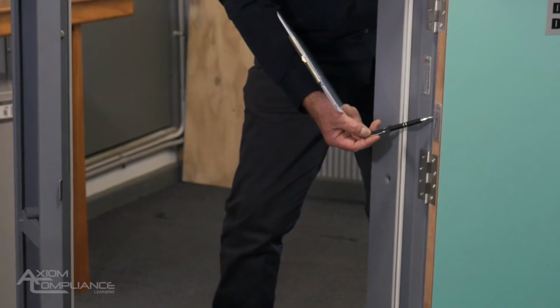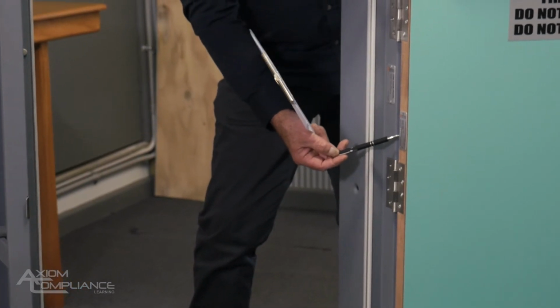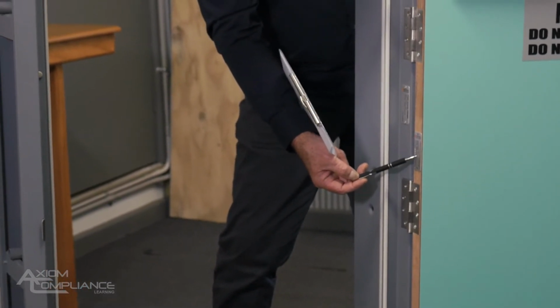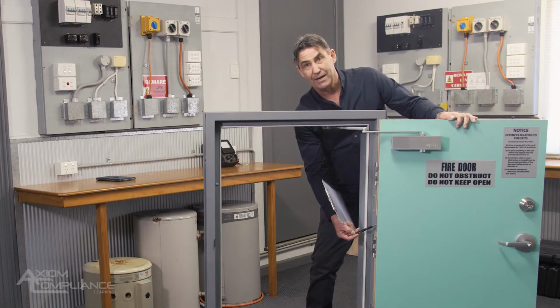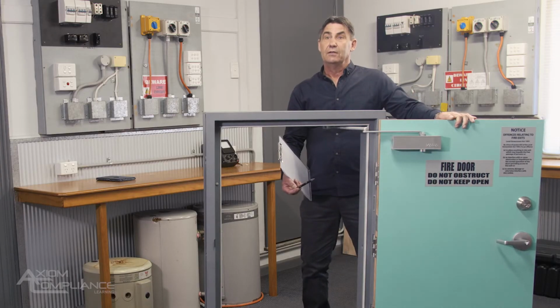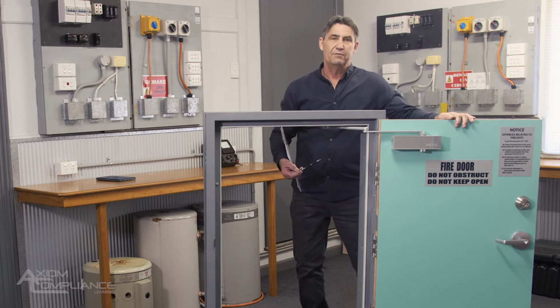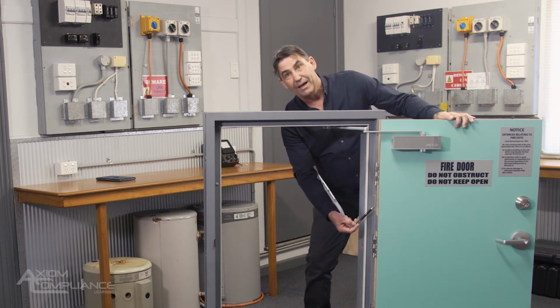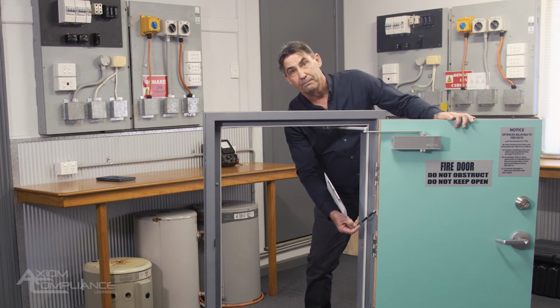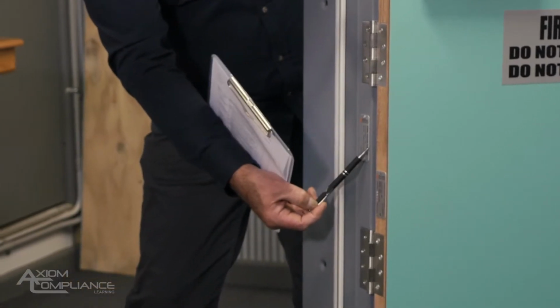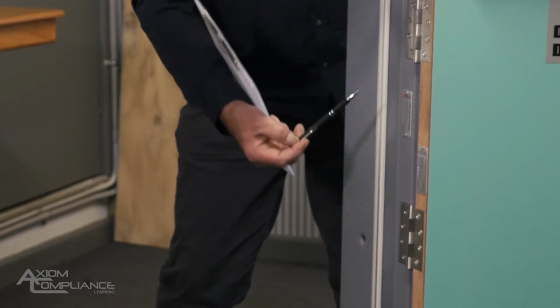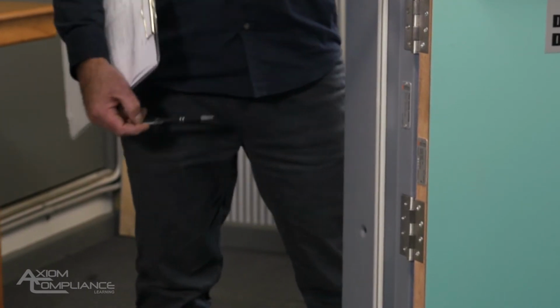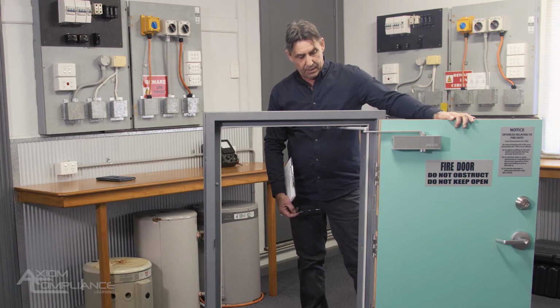And most important is that the door has a tag number on it so that we can identify that tag number with a particular inspection. So the door ID number, if you will, is on that tag on the door. The frame tag doesn't require an ID, okay? So the frame is inspected along with the door. The frame and the door is considered a door set, okay?